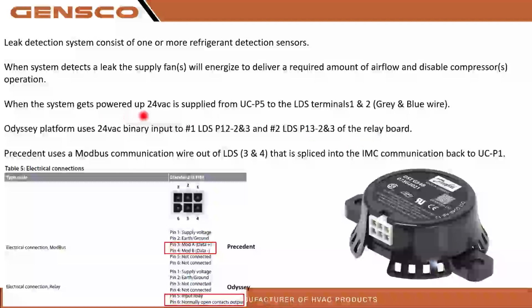When the system gets powered up, 24 volt is supplied from the UC, that's the unit controller, Symbio 7 controller, P5, to the LDS, leak detection system, terminals 1 and 2. So it's got a gray and blue wire. The Odyssey platform uses 24 volt binary, so we can actually test that 24 volt, which makes it a little bit easier. Precedent uses Modbus communication, so we'll be at 4.8 volts DC on LDS 3 and 4. So there's our 3 and 4. We will have this via tech support if we have to get intricate into diagnostics. I'm not going to dive too deep into that right now.